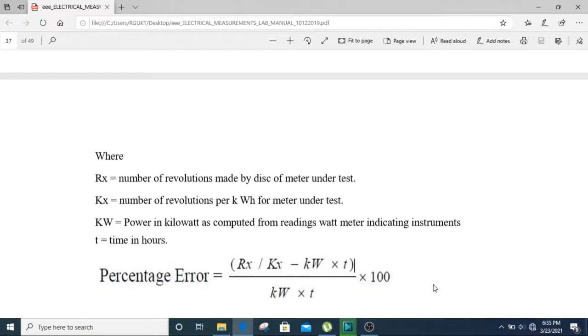This is the energy obtained from the energy meter under test. This is the true energy, voltmeter reading into ammeter reading into the time taken to complete 10 revolutions. Measured minus true, by true energy, into 100, so that you can find the percentage error. This is all about the calibration of a single phase induction type energy meter. Thank you.